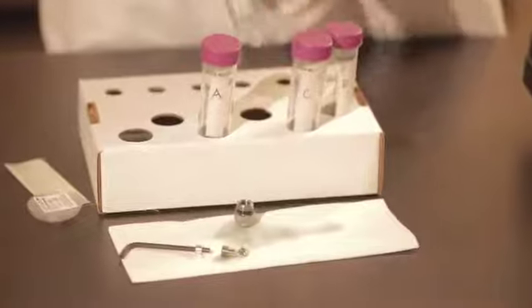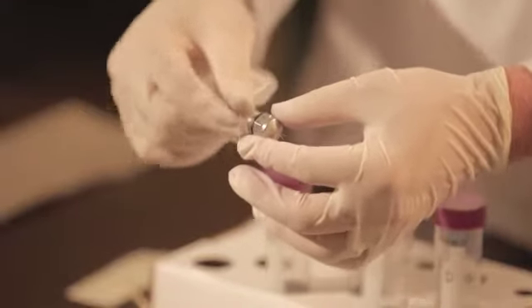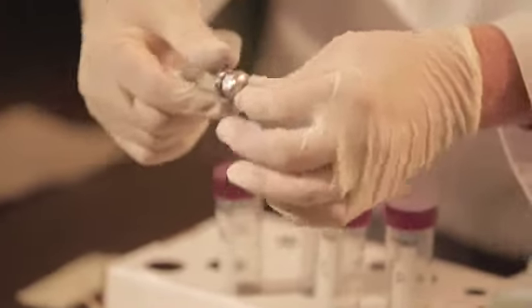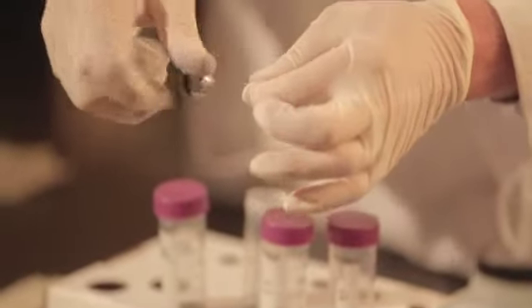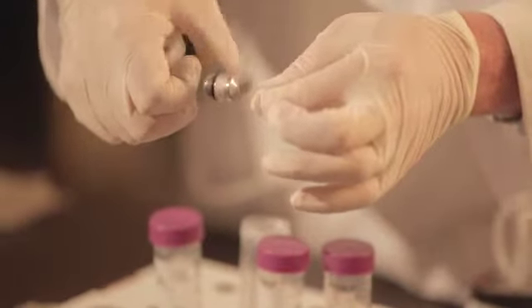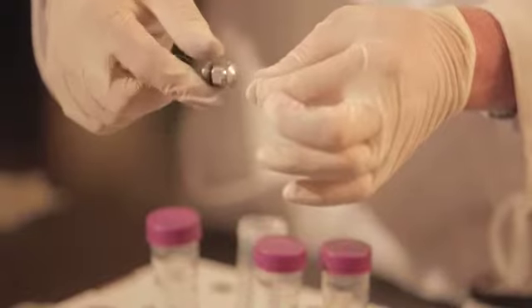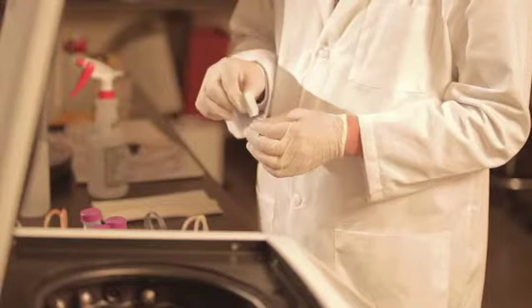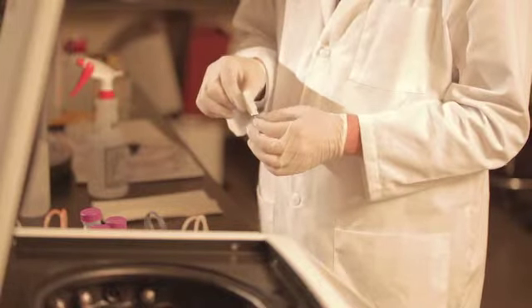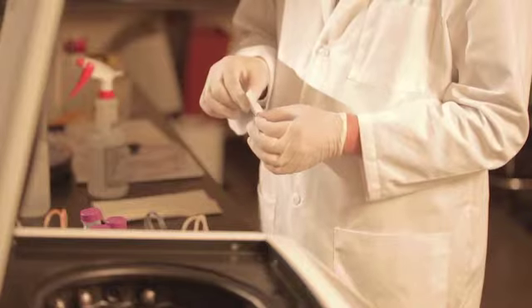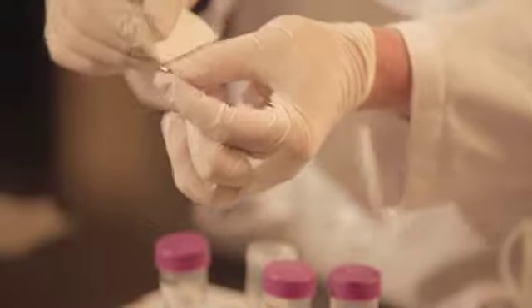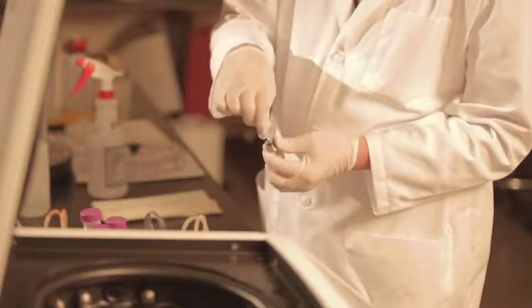Use the copper wire provided to clean the nozzle housing. Run the wire through the housing and then spin the housing on the wire. Also, clean the grooves of the swirl cone with an edge of paper to remove any debris that might be building up in the grooves. Look in the back of the nozzle to make sure debris is not building up. If so, use a cotton swab to remove debris.